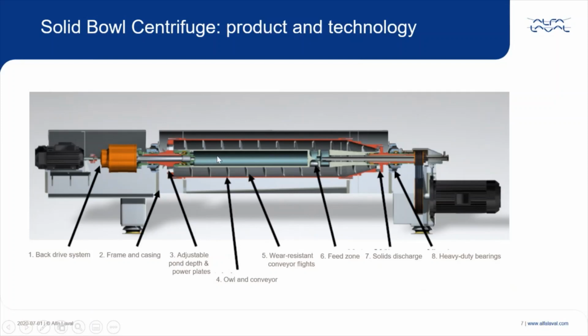Inside the bowl there's a screw conveyor, a helical screw. Both the bowl and the screw conveyor rotate in the same direction, and these are rotated with the help of two motors. On the right side is the main motor, which is bigger and drives the bowl. On the left side, on the frame, is a small motor connected to the screw conveyor located inside. The rotating assembly - the bowl, the conveyor, as well as the gearbox, which is in orange color - sits between the back motor and the rotating assembly.